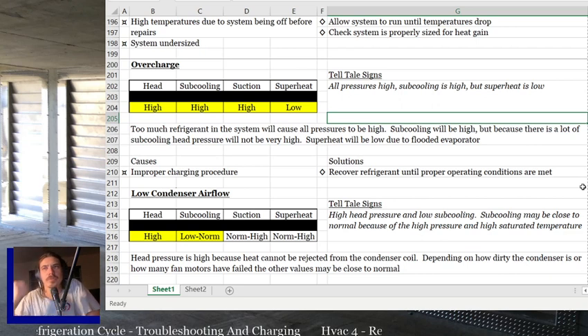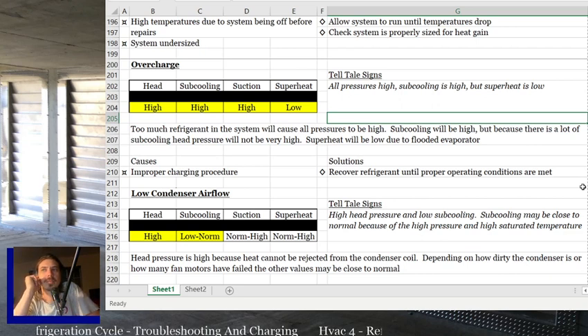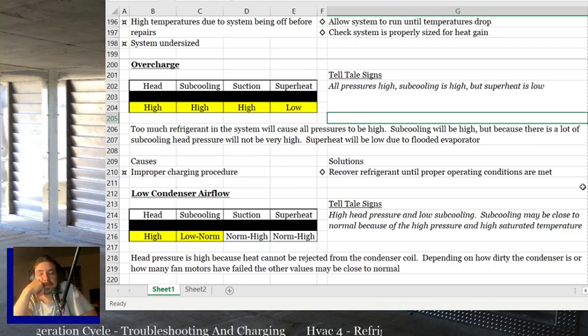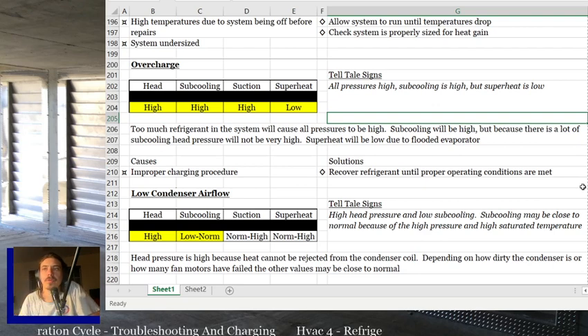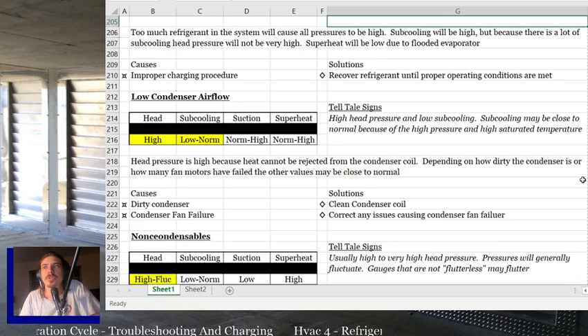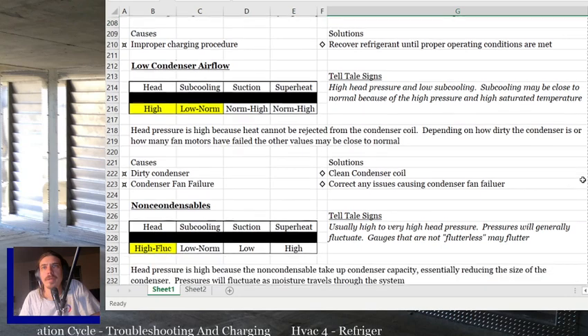So too much refrigerant in the system will cause all pressures to be high. Subcooling will be high, but head pressure will not be very high. Superheat will be low due to the flooded evaporator. Causes: improper charging, I mean, period. Too much refrigerant is too much refrigerant. You can't put too much refrigerant unless you didn't know what you were doing. And then the solutions are recover refrigerant until proper operating conditions are met, or weigh it back in.